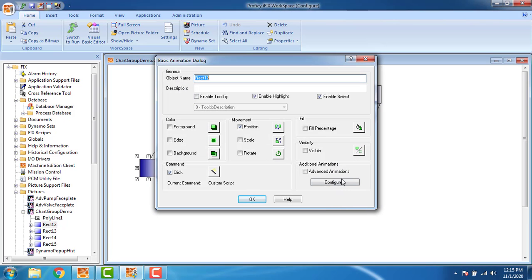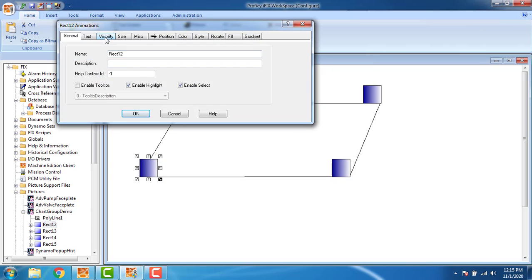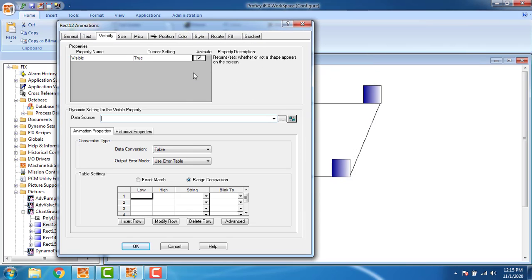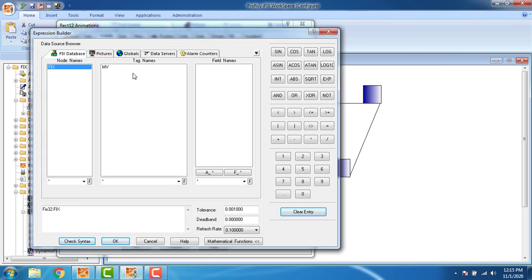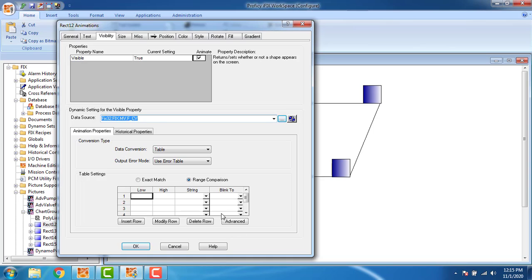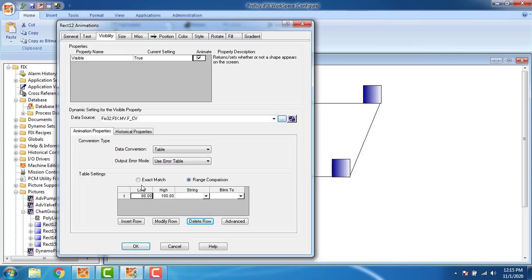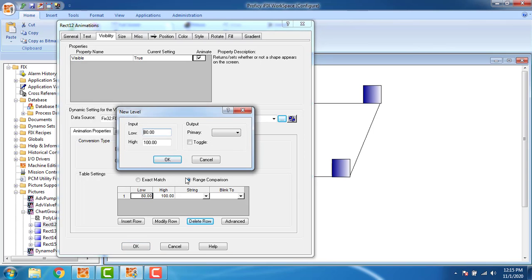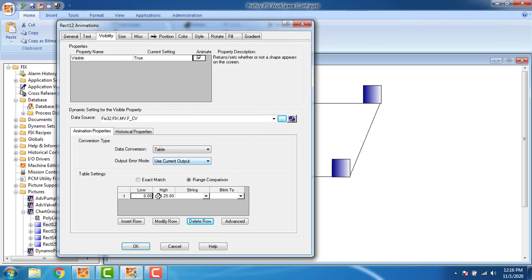To set visibility, double-click the first block, go to Advanced, then Visibility — you can see 'true'. Assign the tag 'mv', click OK. Delete the other rows, select range comparison, use current output. The low value is 0 and the high value is 25 — so from 0 to 25 the first block will be visible (true). Click OK.